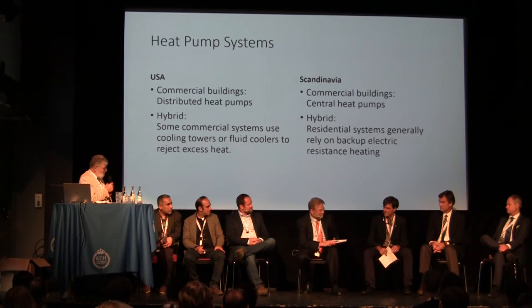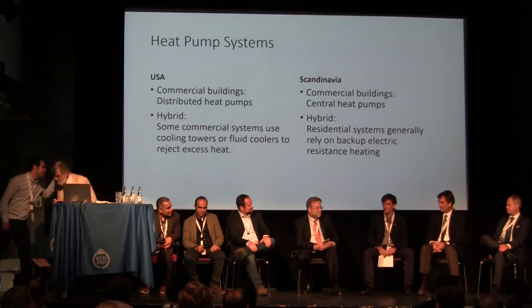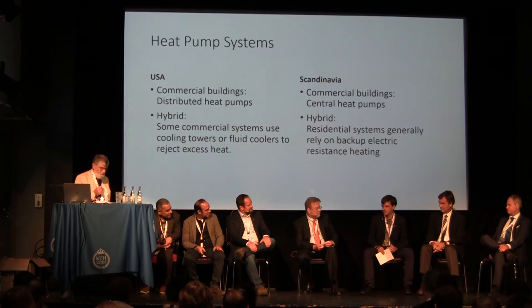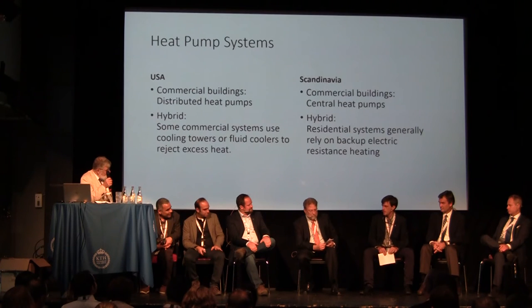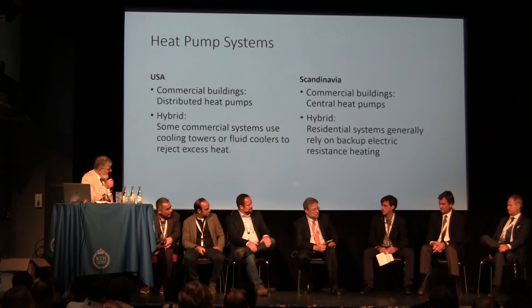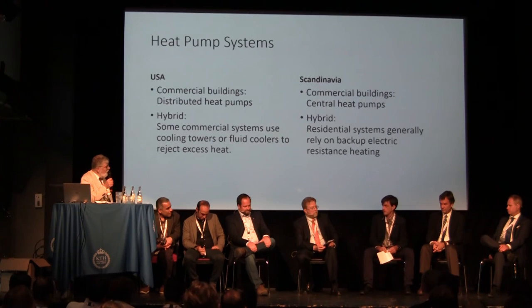Thank you for inviting me to talk about G-functions and the Ashrae method in a place where many people have made great research. I'm thinking of Professor Spitler, and also people from Lund University and Chalmers University. What I can contribute is that in Italy, regarding the design procedure, we are in between the Swedish and US traditions. We adopted the Ashrae standard for designing borehole fields, but our national standard also allows the use of different methods based on superposition of G-functions, using the knowledge of the monthly heat loads at the building side.